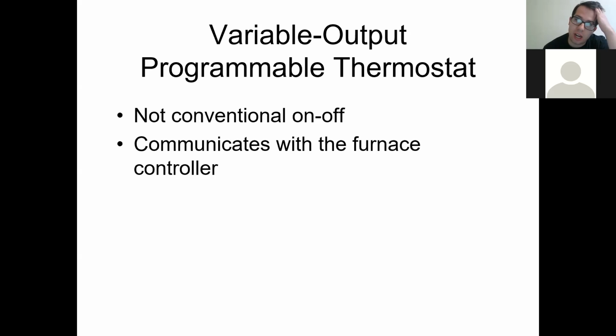Those communication wires for the thermostat to the control board are extremely important. You have to make sure they aren't getting damaged, bent, or stressed in any direction. If they're bent or broken in any way, it's not going to carry a clean signal or that code, and the system won't be able to kick on and work properly. That's the biggest threat we've got.